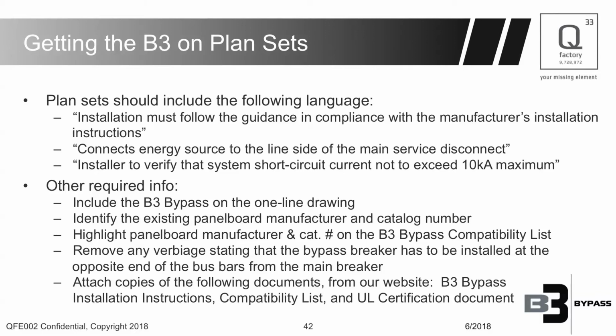Remove any verbiage stating that the bypass breaker has to be installed at the opposite end of the bus bar from the main. That no longer applies because we're not on the load side, we're on the line side. Attach copies of the installation instructions, attach copies of the compatibility list, and the UL certification. This is just a best practice. If you know your counter people do not require hard copies, don't attach it. But what we've seen, it's a newer product. Attach as much as you can so they don't come back to you.